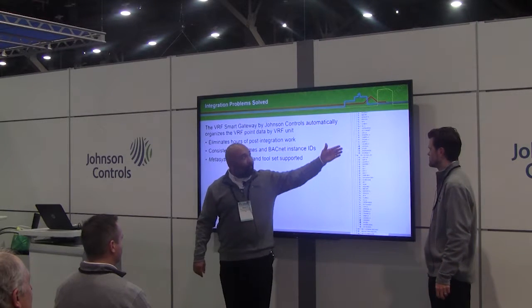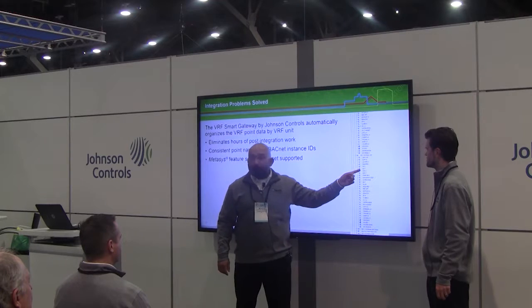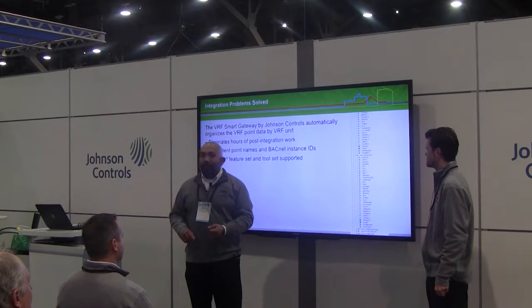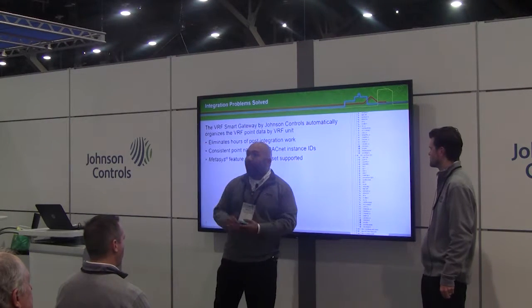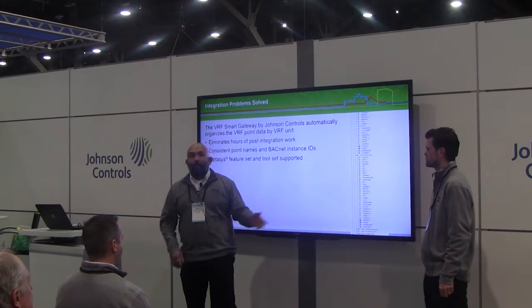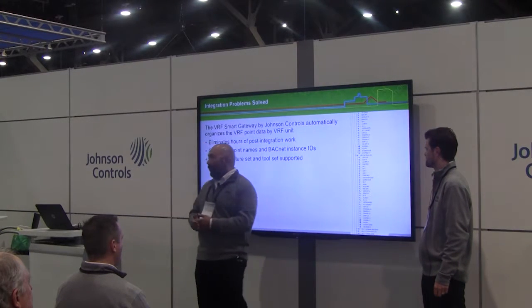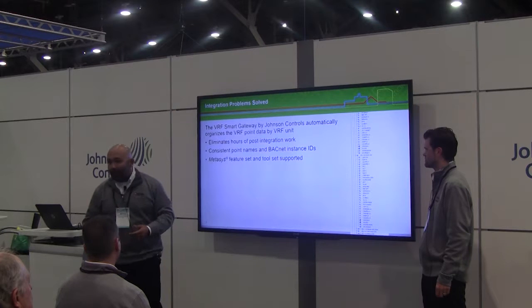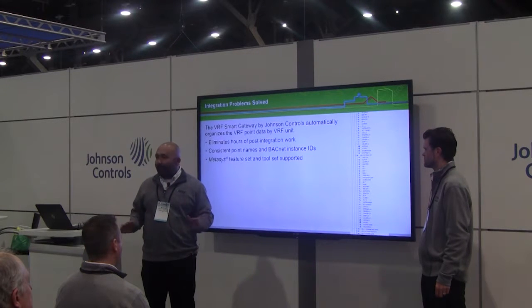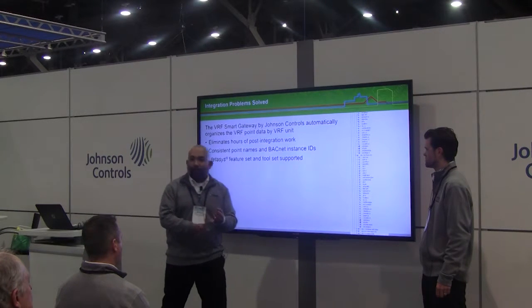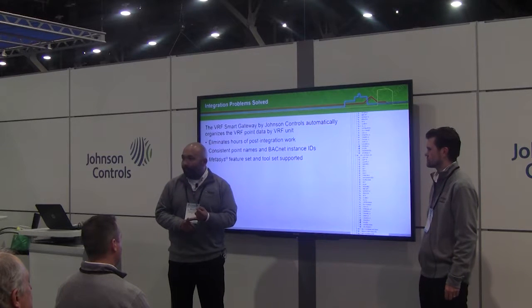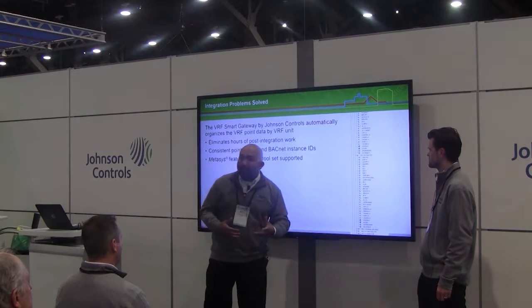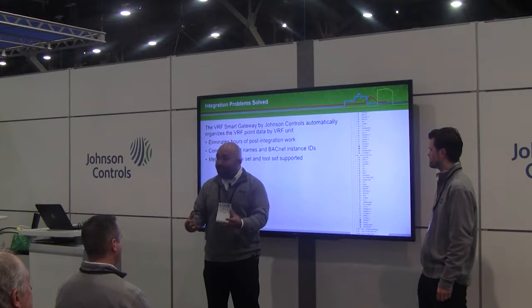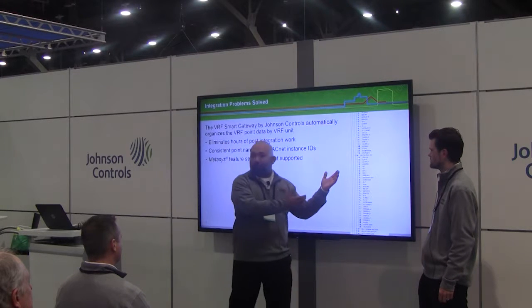Let's look at some of the information we get from the equipment—everything from return air to supply air, and how much frequency we're requesting from the outdoor set of units. Why is this beneficial? Because on most front ends we actually have to add extra sensors. Not anymore—no more adding an extra space temperature sensor or ambient temperature sensor, because we're taking advantage of all the sensors already inside the VRF system and exposing them to the front end.